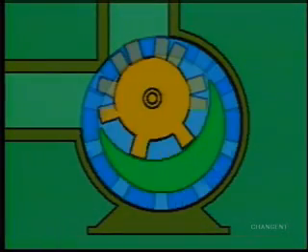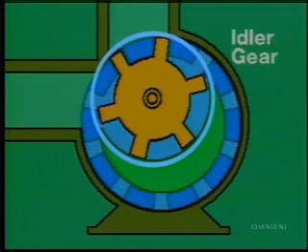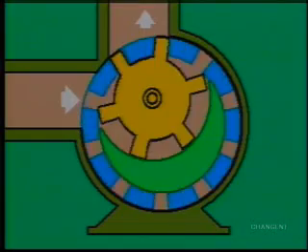Internal gear pumps are built differently from external ones. They have two gears in mesh with each other: the outer, or external gear, which is larger than the internal one, and is called the driver. The internal gear is the driven, or idler gear, of the pump. Fluid is trapped between the teeth of these two gears and is then moved to the pump's discharge section as the two sets of teeth mesh together.